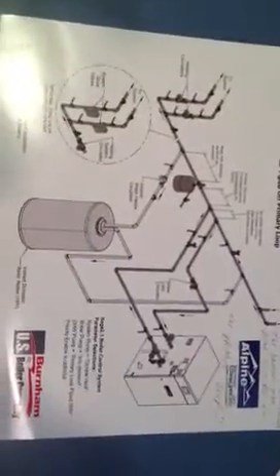This is specifically boiler work for your hot and cold. And by the way this little circle right here is in case you didn't want to have circulators for each zone and you just wanted one circulator and two zone valves. Then that would simply just be the circulator there on the main line, your two zone valves on the T's, your circulator pushing and of course as the zone valve opened the water would go up and through the baseboard and then return the same way into the T's coming back. So whether it be zone valves or circulators direct, you could have these either way. But that's the perfect example of primary secondary piping. Zone valves optional of course.